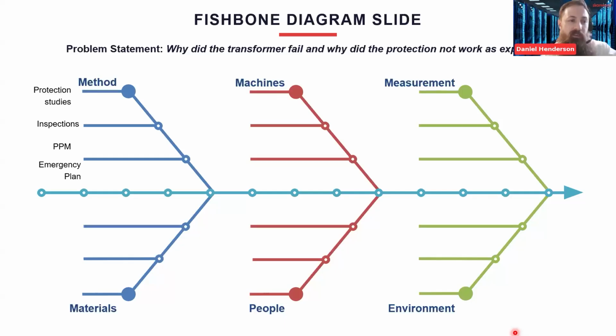The inspection side, so there were inspections. We'll probably cover that a bit more in depth, but just as reference, the process on this site was every 3 months an inspection was done on the substations and the compounds, by a technician following a check sheet, looking for things like debris and housekeeping, so it was all visual. Every 12 months, there was a partial discharge survey and a thermal survey done by a third-party contractor. And then every 4 to 5 years, there was intrusive maintenance done on the assets themselves.